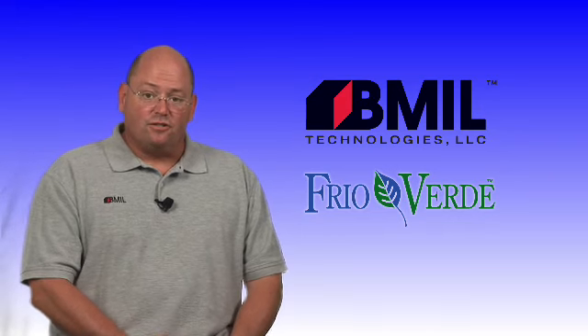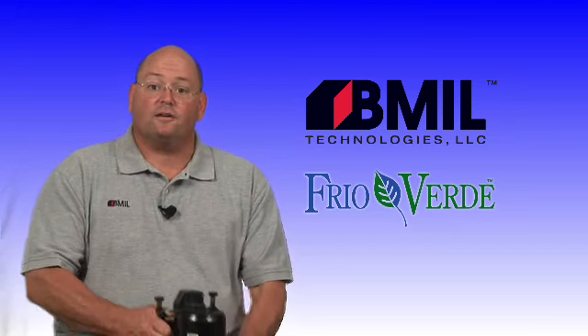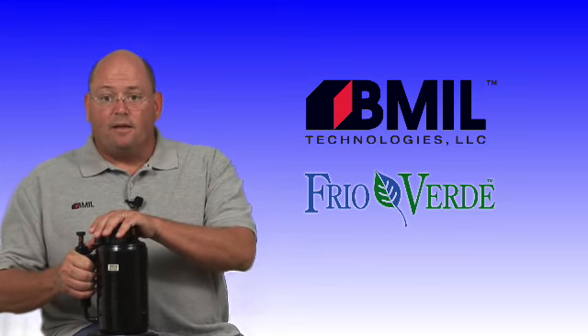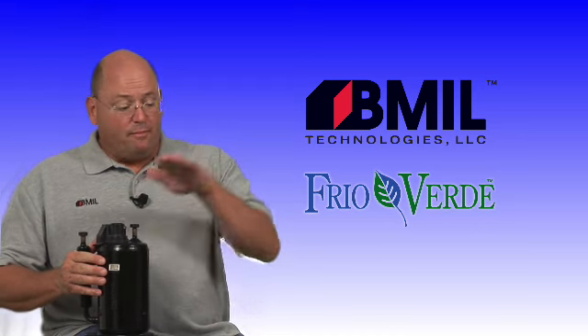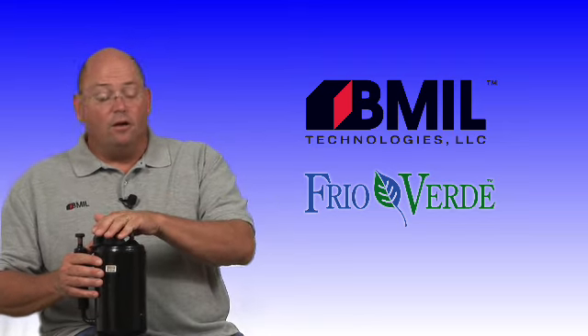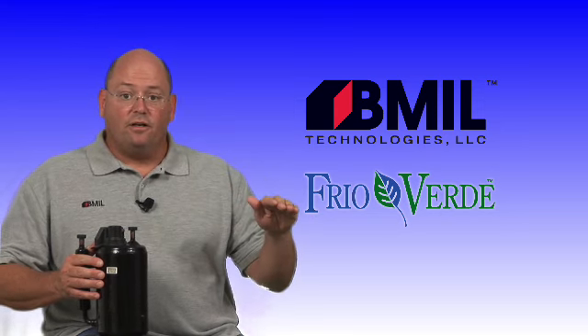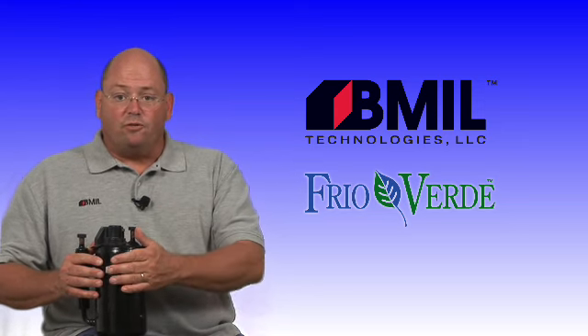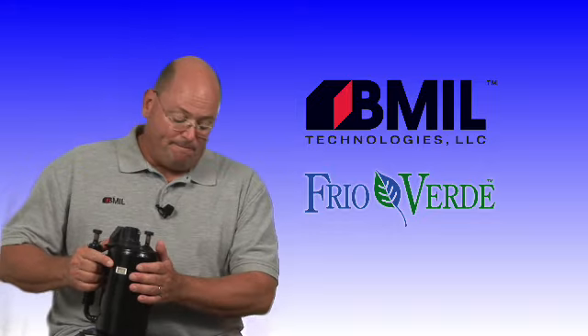Frio Verde matches the mass flow of the subcooling compressor to the mass flow of the 404A compressor. In other words, Frio Verde, this little compressor, is 410A. It's subcooling the main compressor system, but it's matched to that main compressor. And either the main compressor runs with the Frio Verde compressor or neither of them run. They run together. The mass flows are matched. Unlike parallel refrigeration systems, there's not a changing mass flow, so the subcooling compressor is more stable and there isn't this hunting problem which leads to compressor failure.